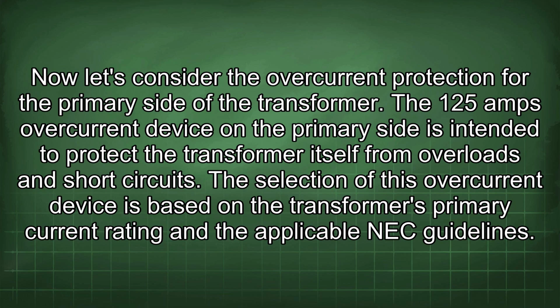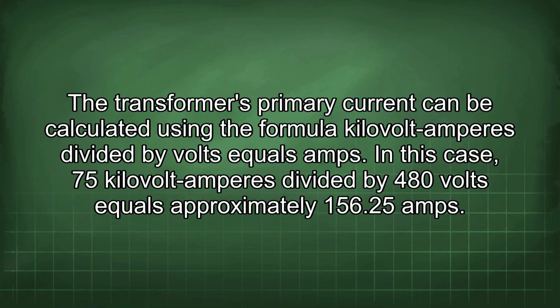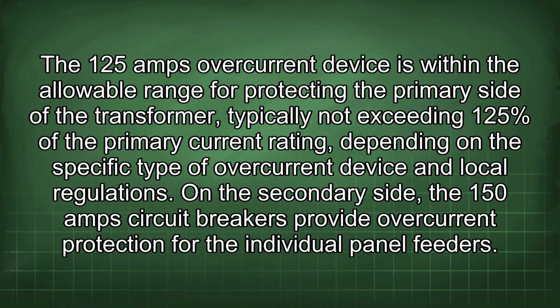The selection of this overcurrent device is based on the transformer's primary current rating and the applicable NEC guidelines. The transformer's primary current can be calculated using the formula kilovolt amperes divided by volts equals amps. In this case, 75 kilovolt amperes divided by 480 volts equals approximately 156.25 amps.